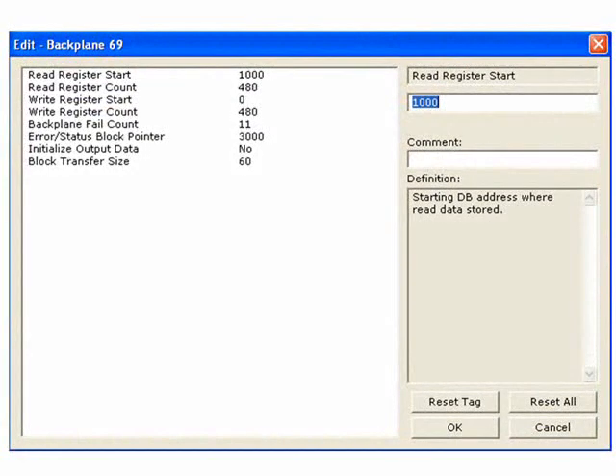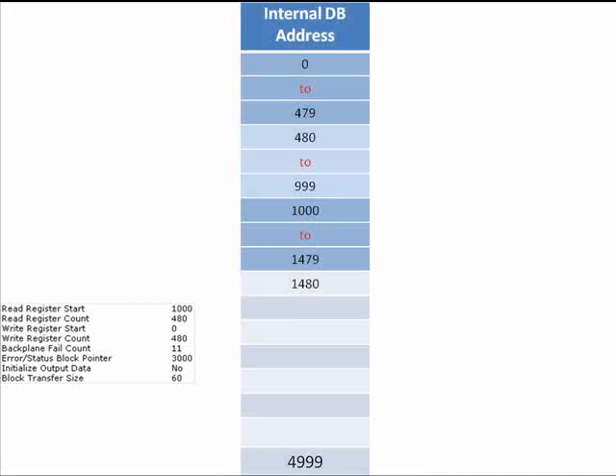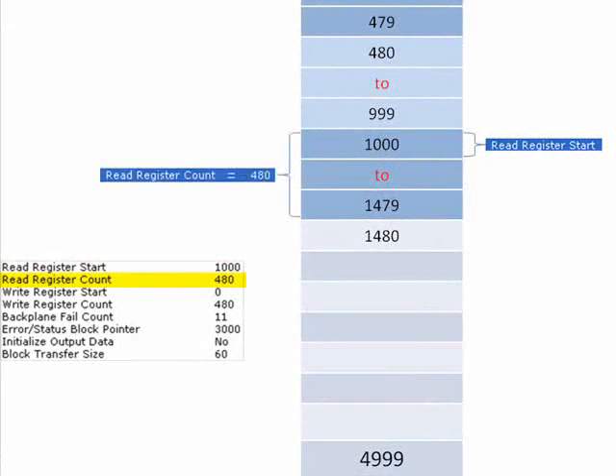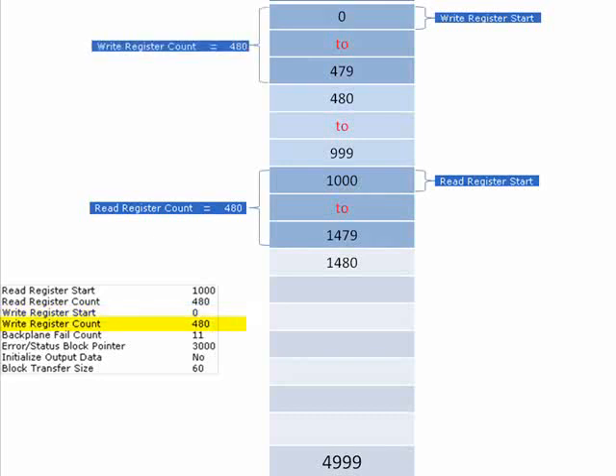Now we see our internal database. The module has 5,000 registers that we can use. Looking at how the database is defined, we break it down into sections. We have our Read Register Start at address 1,000, with a Read Register Count of 480 — meaning 480 values can pass from the Modbus network through the module to the CPU. The Write Register Start is set at 0, also for a count of 480, meaning 480 values can pass from the CPU to the module out to the Modbus network.